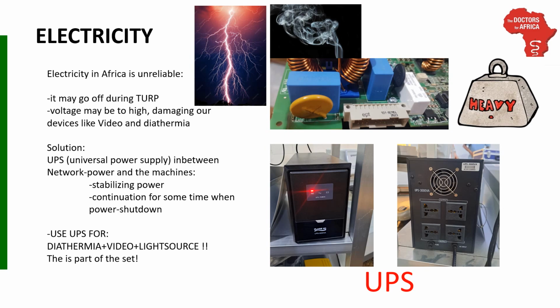The solution is a UPS, the Uninterruptible Power Supply. This reduces the power bursts and lets you continue the TUR when power is down. It will only be able to continue the resection for a limited time. Take care that monitor, light source, camera, and the diathermia all are connected through the UPS. If the network power goes down, the UPS will blink red and start beeping. Beware, the UPS weighs about 25 kilos.